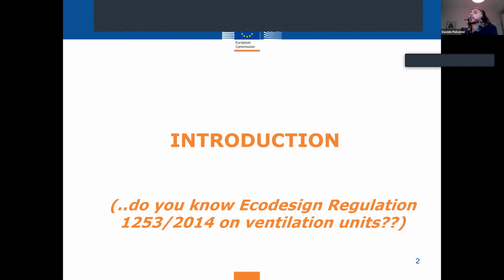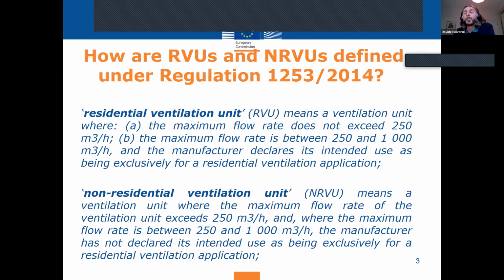Well, you should be aware because via this regulation, we set eco-design requirements since 2016 on all the ventilation units which are placed on the European Union market. The regulation is coupled with another regulation on the energy labeling, which is particularly targeting residential ventilation units. In fact, Regulation 1253, the one on eco-design, foresees a basic classification between the RVUs, the residential ventilation units, and the NRVUs, the non-residential ventilation units.